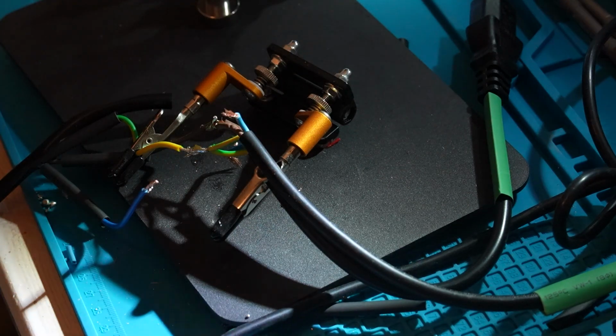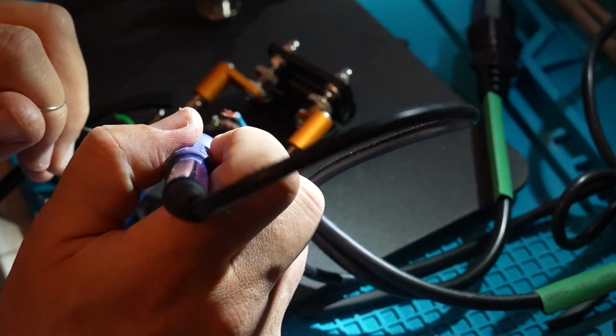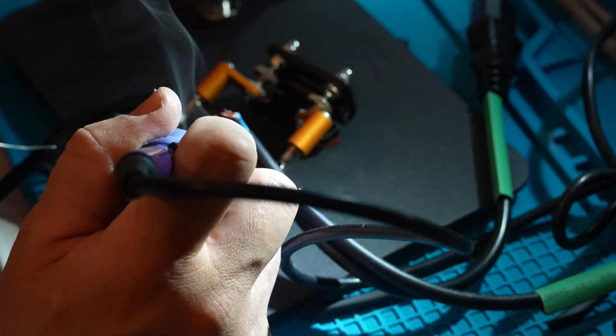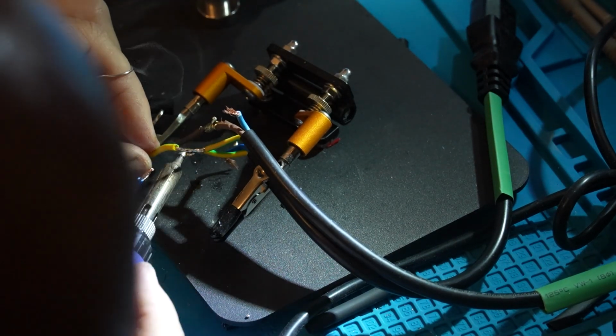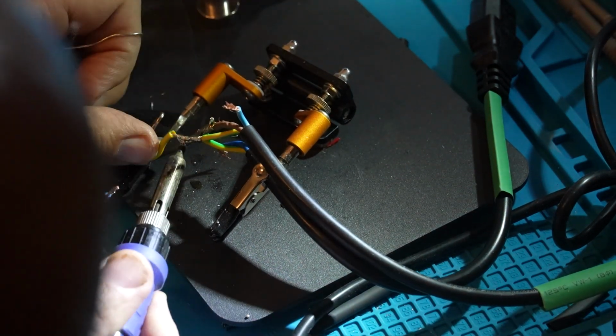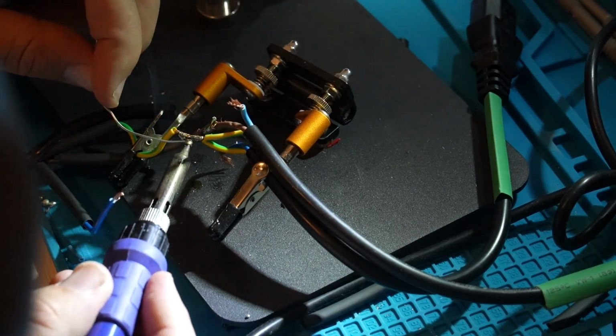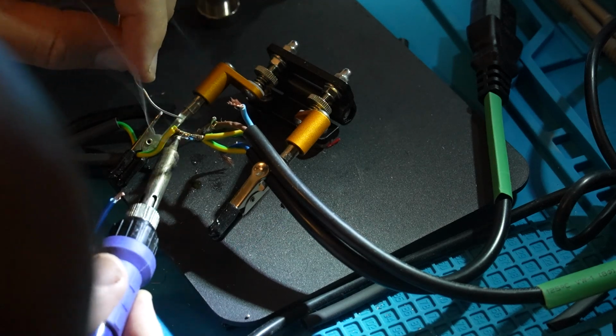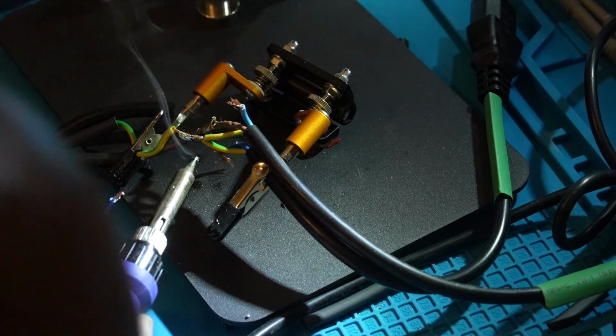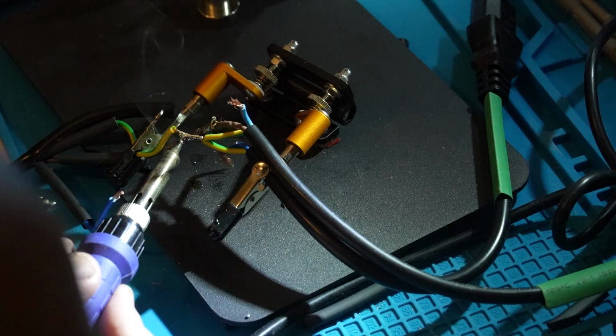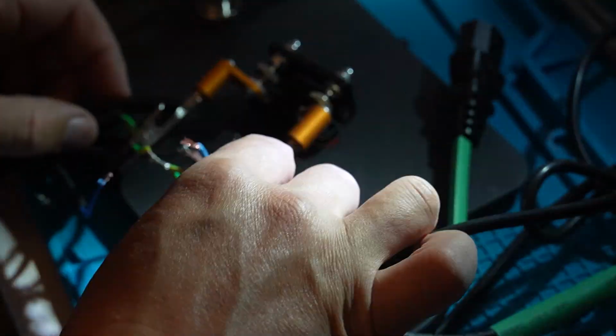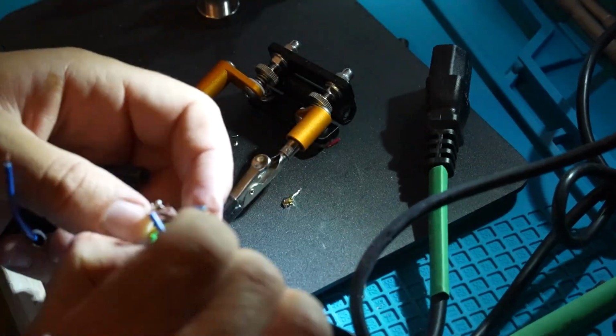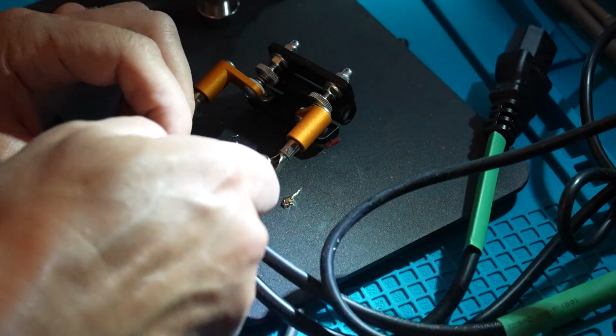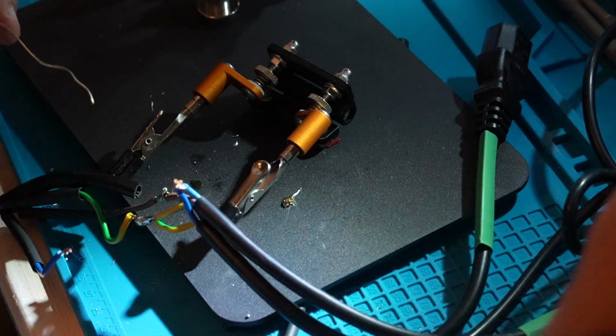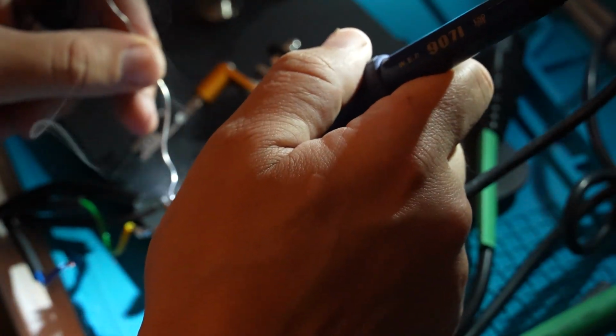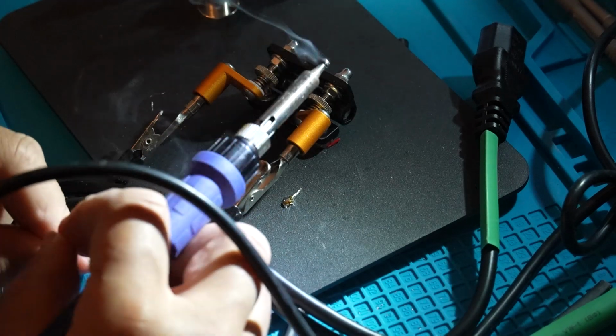I cut and split the same 220 volt wall outlet to power both power supply units from the same socket. While this works for low to moderate loads, you should not do this if you plan to use this setup at its maximum capacity. If you intend to draw high current, it is safer to use two separate wall outlets on different breakers to avoid overloading your wiring and to reduce the risk of fire.